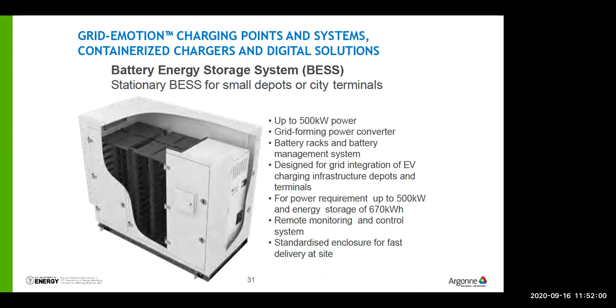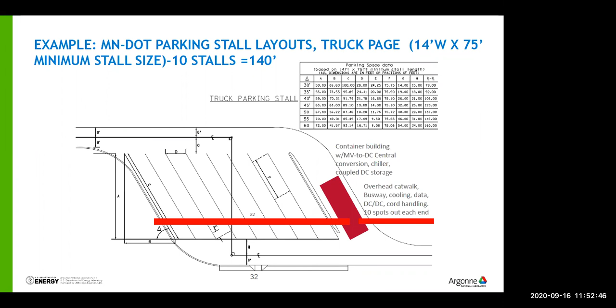So this just shows the obvious. If this red box in the center represents some kind of power electronic solution, the long skinny red bar is some kind of overhead gantry, and then things either drop down or come up from it. So it could either be buried or go overhead, but somehow a radial lead goes from the power conversion and storage to the distribution. It could be that the battery storage is stacked on top of the power electronics, or the power electronics on top of that. Either way, you're going to need some space for an 8 by 20 foot container. These are the DOT guidelines for the angles on how trucks pull in and out. So again, just siting, just awareness. Here's what it could be or should be. Next.